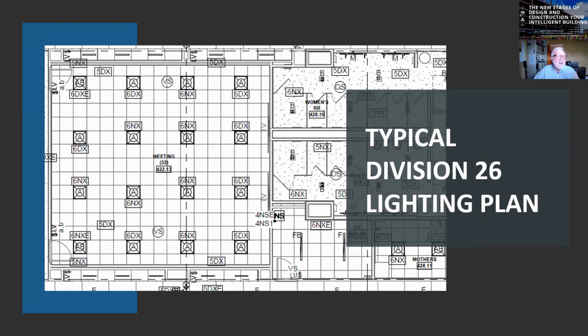Typically on our Division 26 lighting plans now, we show fixture locations for coordination with the ceiling and with mechanical. Here are vacancy sensors—we show those, and we show switch locations. Typically your Division 26 contractor puts a box in the wall and stubs conduit above the ceiling for low voltage. But this is what our lighting plan looks like; we're not showing any details for the POE.